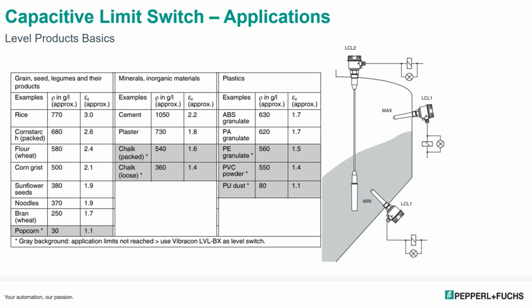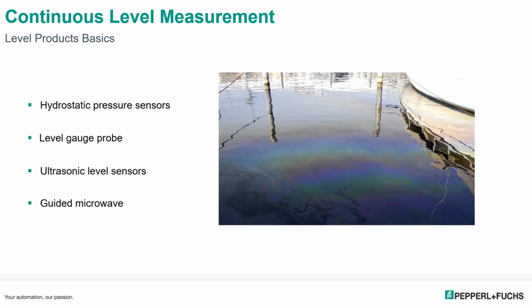The continuous level measurement probes we offer will give you an analog output according to where the height of the medium is in the tank. What we have to offer as far as continuous level is the hydrostatic pressure sensors, the level gauge probes, which is another type of pressure probe, ultrasonic sensors, and the guided wave radar systems and the radar microwave systems.